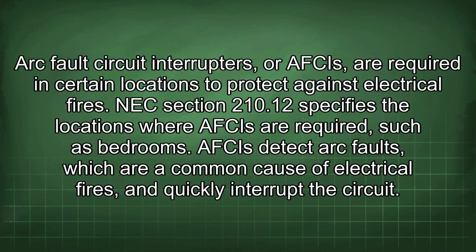Arc fault circuit interrupters, or AFCIs, are required in certain locations to protect against electrical fires. NEC Section 210.12 specifies the locations where AFCIs are required, such as bedrooms. AFCIs detect arc faults, which are a common cause of electrical fires, and quickly interrupt the circuit.